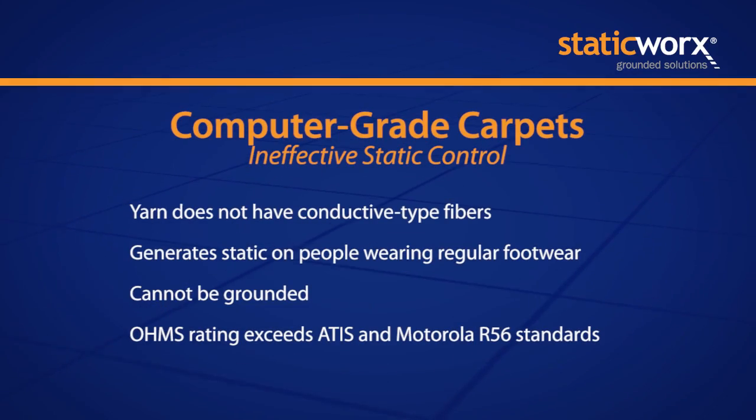We don't like computer-grade carpet tile for these spaces because what we've discovered is it only prevents people from getting static shocks. It does not prevent circuit boards inside of servers from being disrupted by static charges. And that's because when you eliminate a shock hazard using a floor, all you're doing is preventing the floor from generating charges over 3,500 volts. Computer equipment is sensitive to 20, 40, 50, very low numbers of volts.